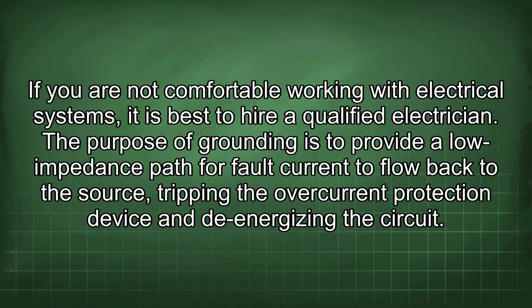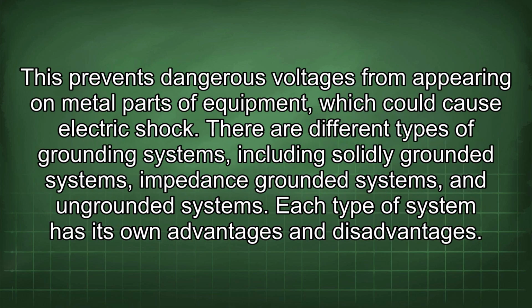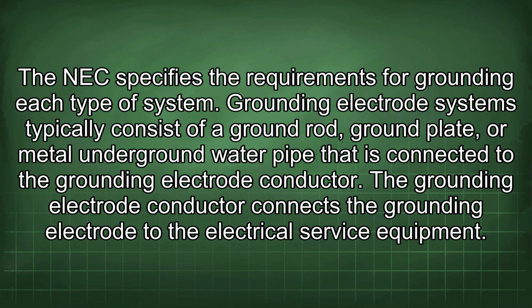The purpose of grounding is to provide a low impedance path for fault current to flow back to the source, tripping the overcurrent protection device and de-energizing the circuit. This prevents dangerous voltages from appearing on metal parts of equipment, which could cause electric shock. There are different types of grounding systems, including solidly grounded systems, impedance grounded systems, and ungrounded systems. Each type of system has its own advantages and disadvantages. The NEC specifies the requirements for grounding each type of system.